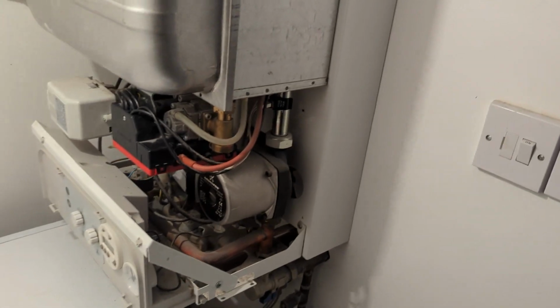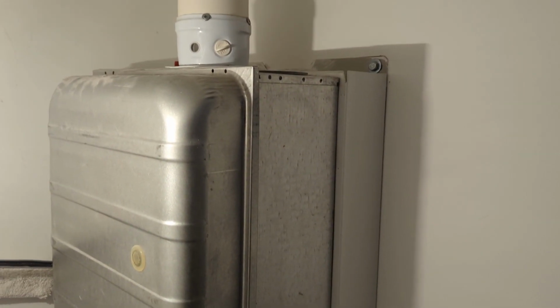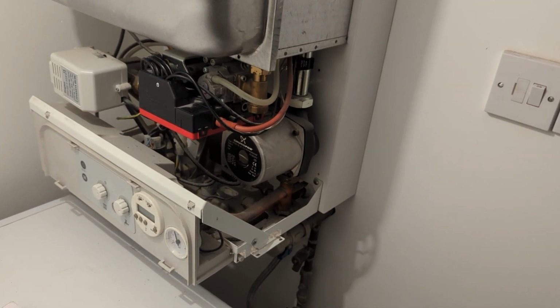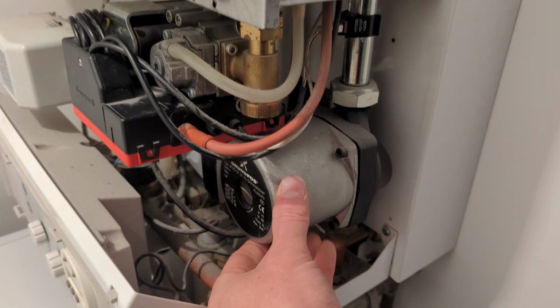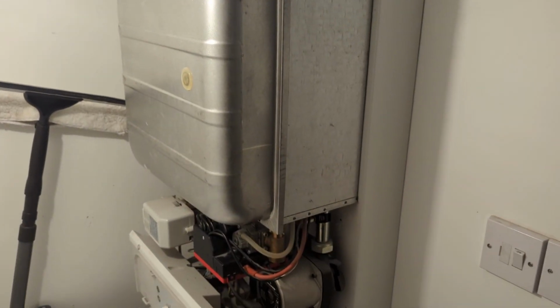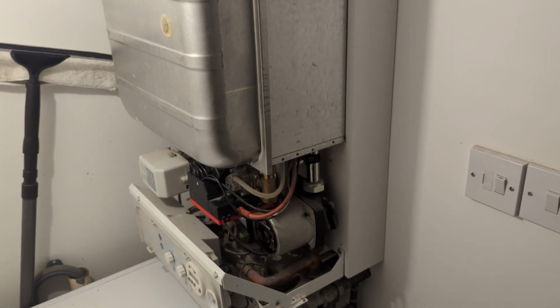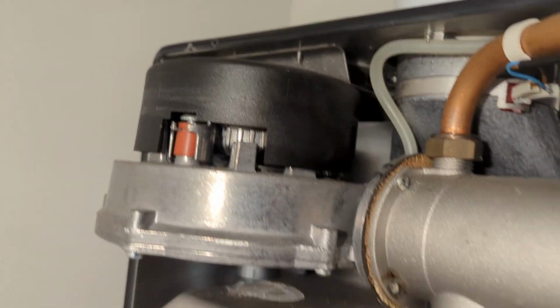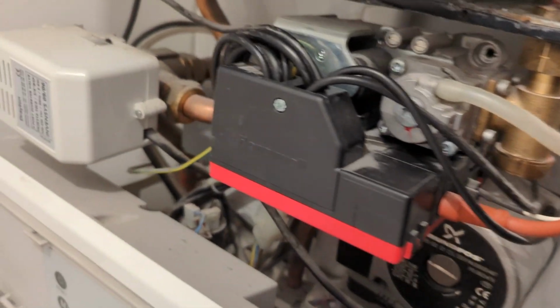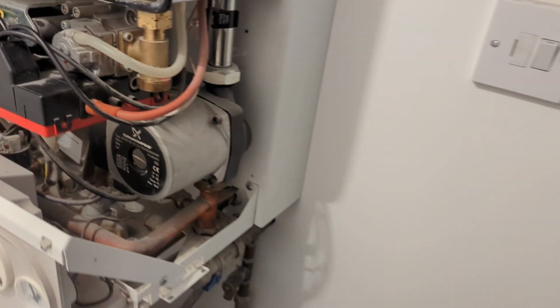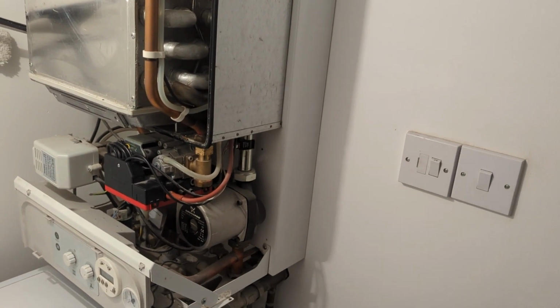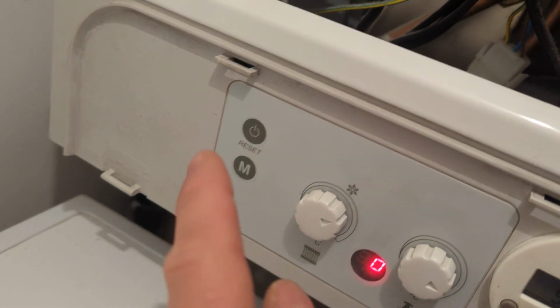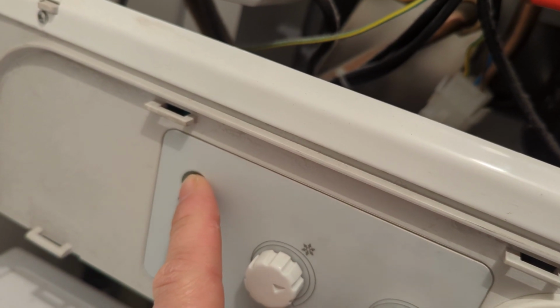the boiler would go into its purge cycle. As you can hear the fan coming on, the pump comes on, they both come on for a short time. For example, the fan's coming on just to purge any potential unwanted gases in the heat exchanger. But it proves that the fan is actually working and spinning, which you can hear. Again, the pump, I could feel that had come on as well. So these components were working, but not coming on when heating or hot water was demanded.